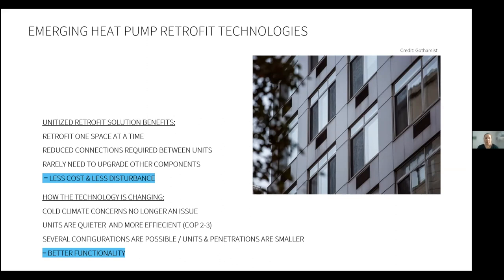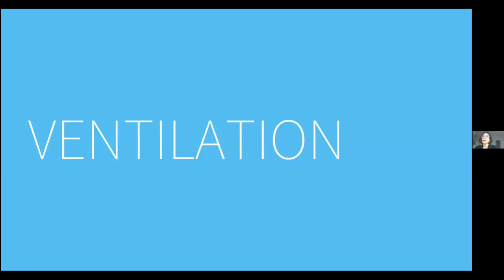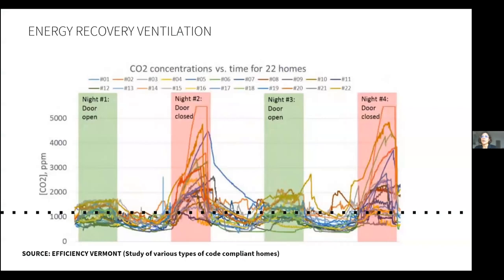We are currently using them on these two new construction projects and reviewing them for retrofit. We see a huge potential for them in this retrofit market to replace old gas PTACs. However, we would really like to see more manufacturers get into this market. Now we will touch upon how we provide ventilation, the strategy for which is critical to a healthy and well-performing building. We're getting more data on how code minimum ventilation is not really providing true air changes of fresh air. An example of a dangerous result is CO2 buildup at night.